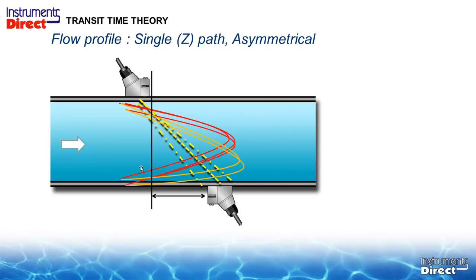Same thing when you get more disruption and you have an application with a short run of pipe with a variable flow rate. So the flow goes up and down, so the mean velocities move all over around inside the pipe. So in this case, you may come out to the pipe on Monday morning with low flow rates, have to move the sensor here, you get a reading, then come out in the afternoon and the flow rates are higher, you may have to move the sensor again to actually pick up the signal.